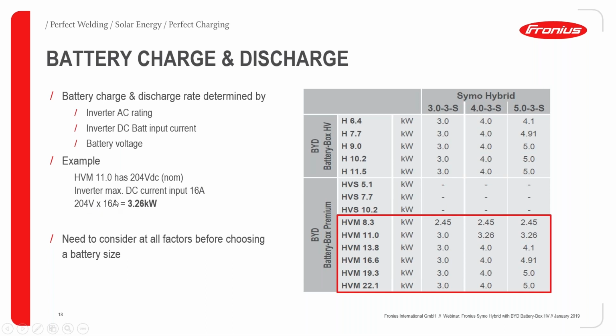The other thing is the battery voltage—that'll determine it too. Let's look at an example. I've put the HVS in there, but it's blanked out because it's not compatible with the Symo Hybrid. The HVM series gives you a table as to which battery and which inverter will give you what charge and discharge rates. For example, HVM 11 has roughly 204 volts DC nominal, times 16 amps gives you 3.26 kilowatts. So if you've got a 3 kilowatt inverter, you'll only get 3. If you've got a 4 or 5 kilowatt inverter, you'll get the full 3.26. To get the full roughly 5 kilowatts, you'd need around 16 kilowatt hours for the HVM in a single stack. Make sure you consider that when sizing the battery.